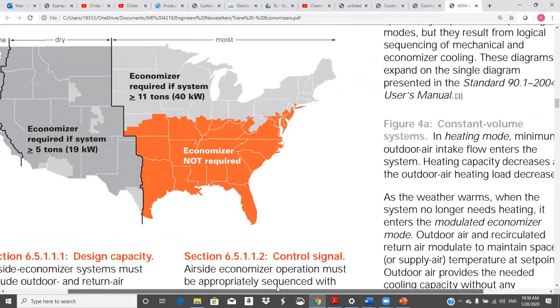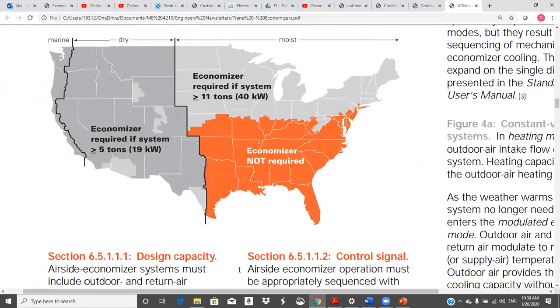Here we go. This document's a little bit old. I don't know if this has changed since it was published, but basically you see the parts of the country where it's warm and moist a lot, and not so much up here. If it's greater than 11 tons, economizer required; if the system is greater than 5 tons. So you see out west for sure. I think it is now around here too. ASHRAE 90, they come out with a new version of these standards every 3 or 4 years. So, like I said, this thing may be a little bit dated.